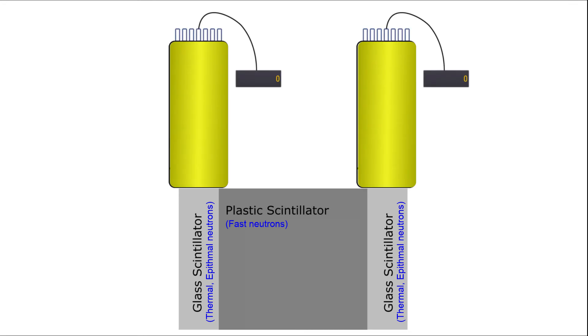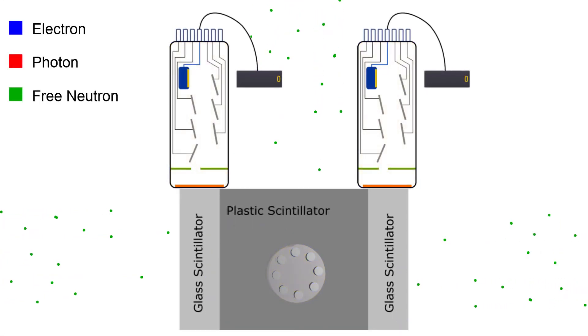The two glass detectors face opposite directions from each other. The plastic detector is at a 90-degree angle relative to the glass pair. Since these detectors are directional, they can only detect neutrons coming from the direction they're facing.